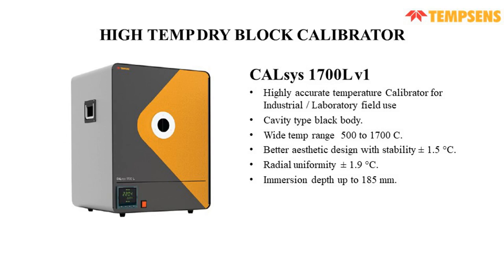This is CALsys 1700L. This is a cavity type black body. It has a range of 500 to 1700 degrees centigrade with a stability of 1.5 and a radial uniformity of 1.9 degree. If you insert a block, it will work as a 1700L, and it can have a cavity, so it will work as a black body also. It has an immersion depth of 185.